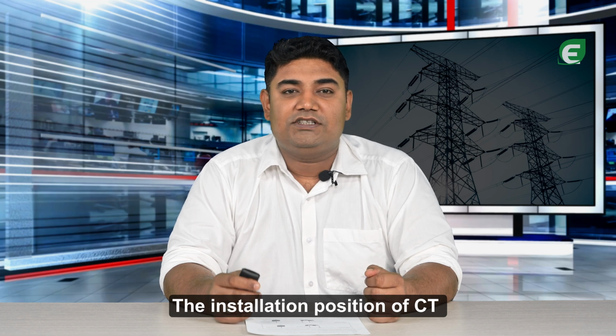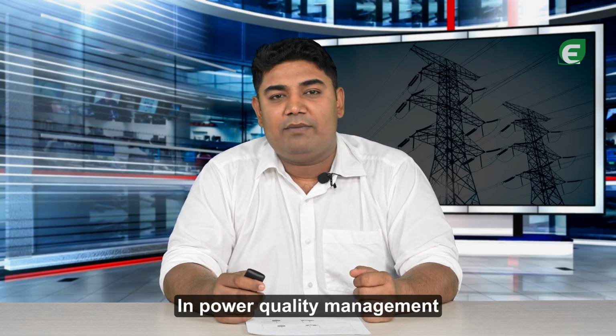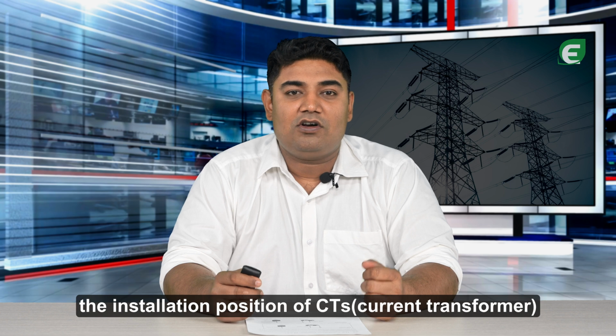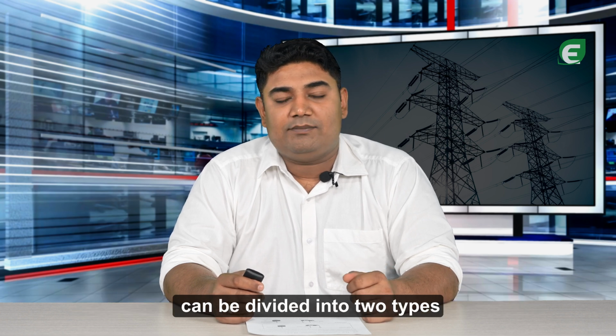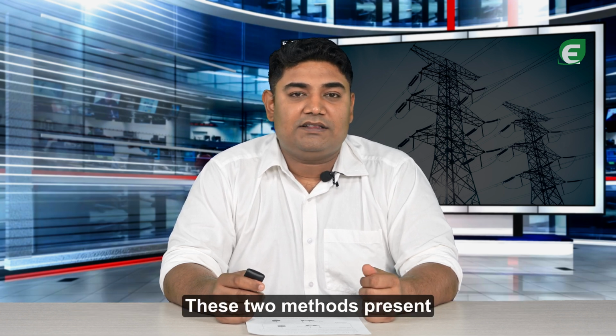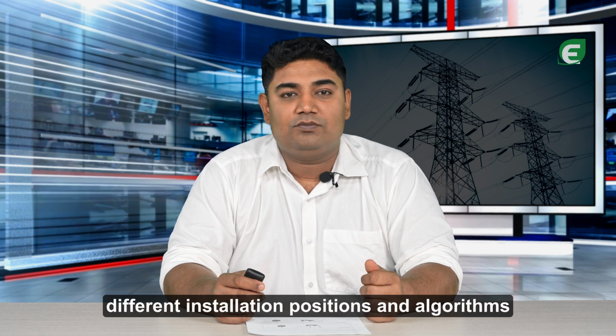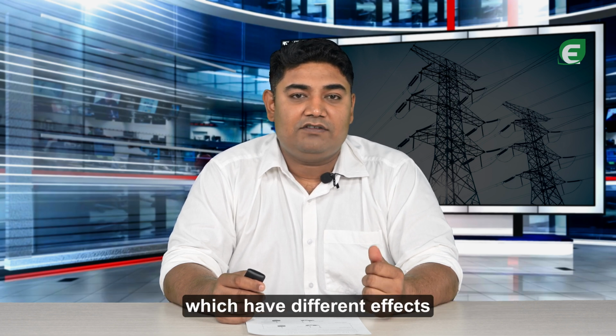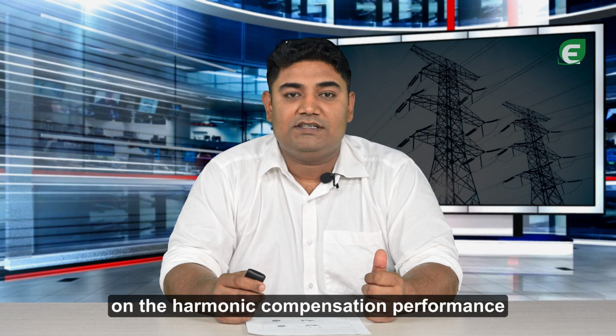The installation position of CTs. In power quality management, the installation position of CT can be divided into two types, open loop and closed loop. These two methods represent different installation positions and algorithms which have different effects on the harmonic compensation performance.